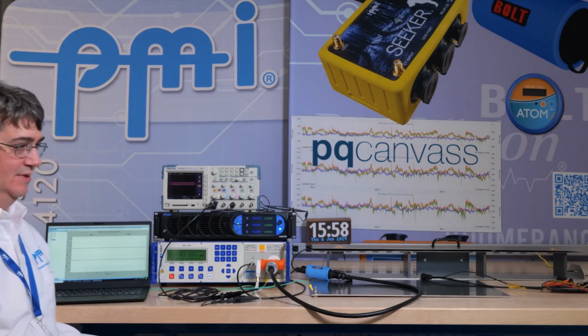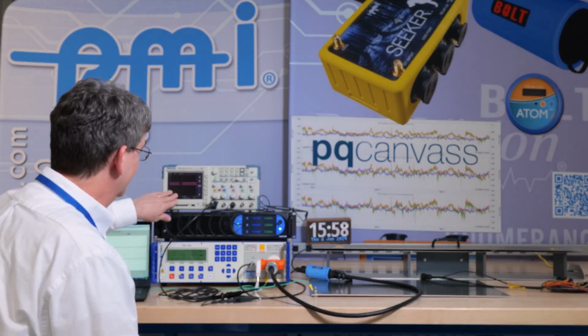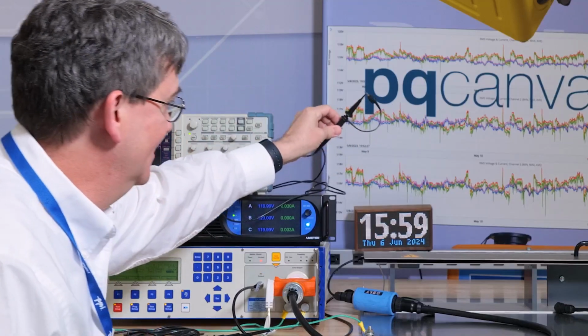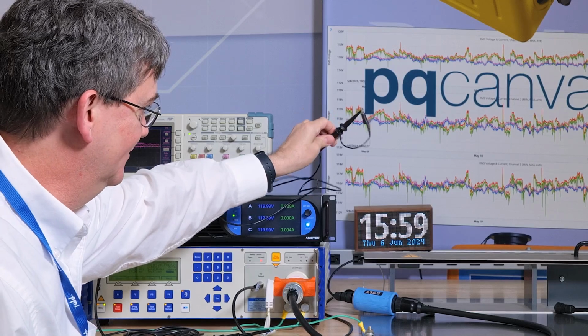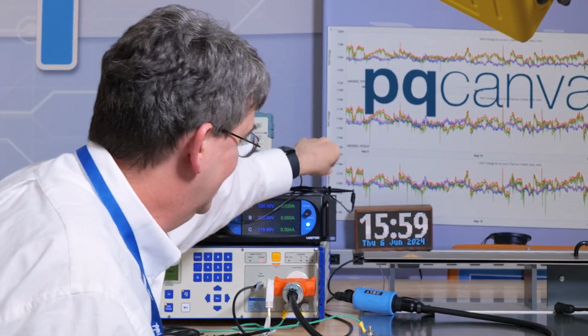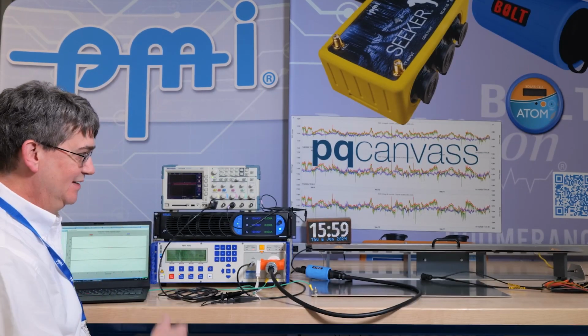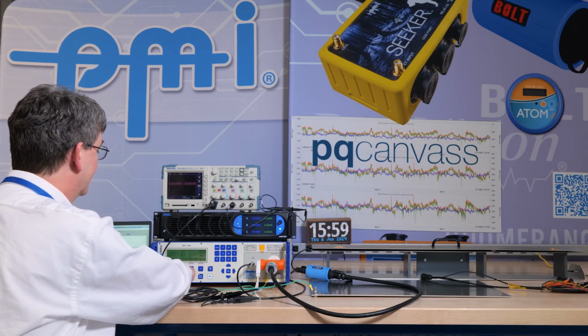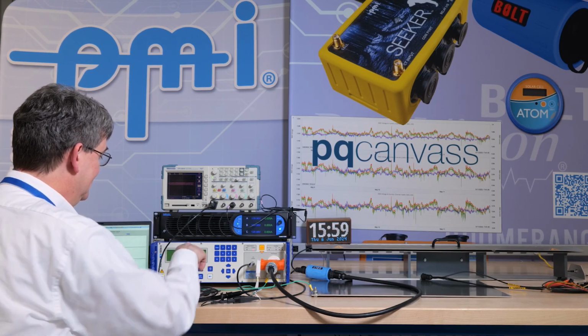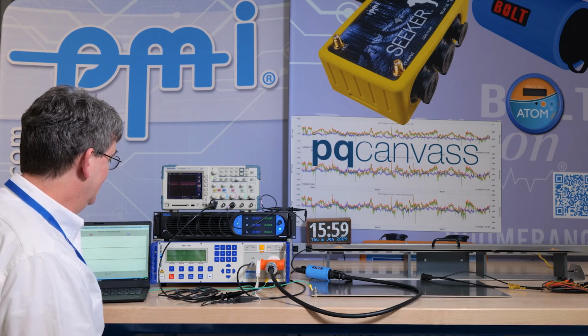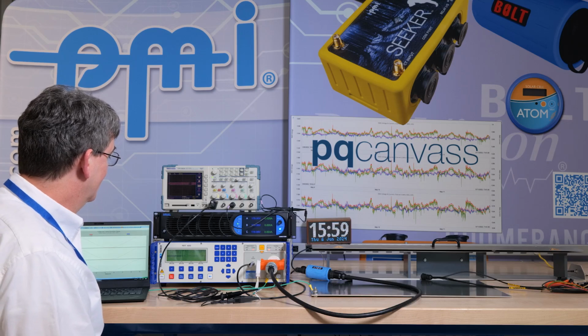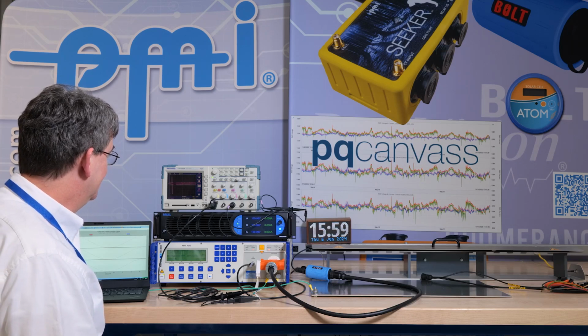And we're still connecting Wi-Fi to make sure the bolt is still functioning normally. And here in the scope, we're actually just using a probe connected to itself as a tiny loop antenna, just to pick up the radiated field to verify that we are pulsing. So I'll run the test. This is a 10-second test, and the machine warms up. And then we can see the pulses applied.